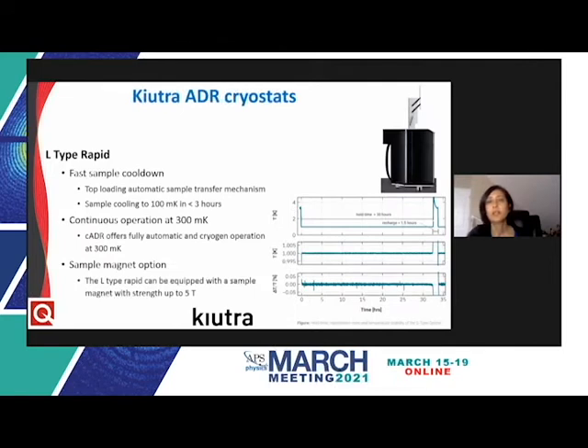Kiutra's L-type Rapid features a larger cylindrical vacuum vessel that can integrate up to four magnetic cooling units arranged in a circular pattern. Its key feature is a proprietary puck-based top-loading sample exchange mechanism, which allows automatic transfer of samples to the low temperature stage, cooling to a minimum of 100 millikelvin within less than three hours. In standard configuration, it allows continuous cooling to 300 millikelvin, supports up to 40 DC and four RF connections, and can be equipped with an optional five Tesla sample magnet.